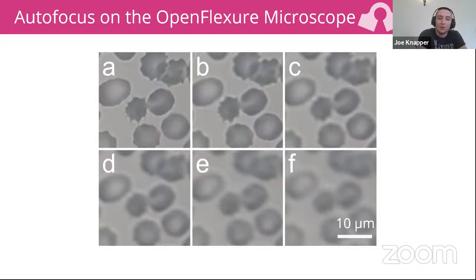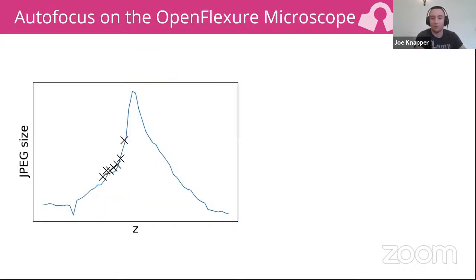To account for this, we added extra steps to the autofocus software when working on blood samples, adding a version of closed loop scanning which measures the sharpness of images as they're taken. We'll only accept that an image is sufficiently sharp when the images around it indicate that the system has focused. If it doesn't get to a point that it's happy it's focused, it will abort and automatically restart that stack.